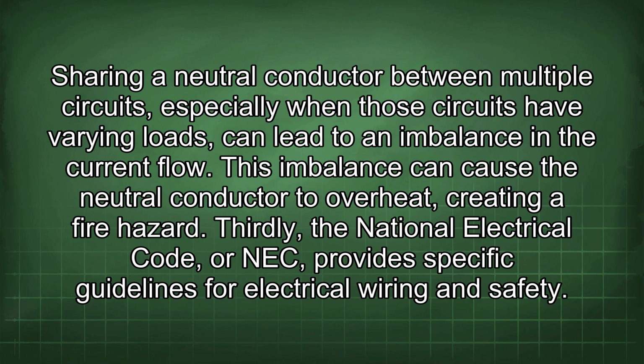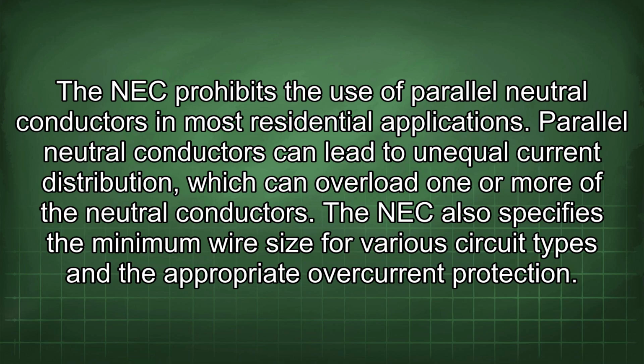Sharing a neutral conductor between multiple circuits, especially when those circuits have varying loads, can lead to an imbalance in the current flow. This imbalance can cause the neutral conductor to overheat, creating a fire hazard. Thirdly, the National Electrical Code, or NEC, provides specific guidelines for electrical wiring and safety. The NEC prohibits the use of parallel neutral conductors in most residential applications. Parallel neutral conductors can lead to unequal current distribution, which can overload one or more of the neutral conductors.